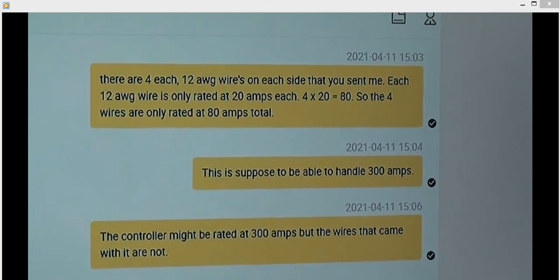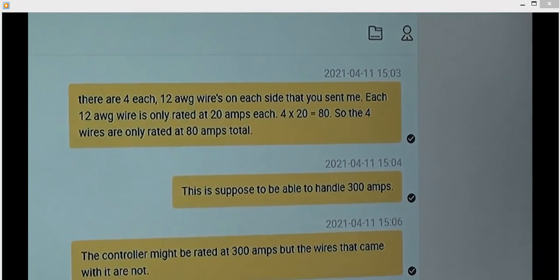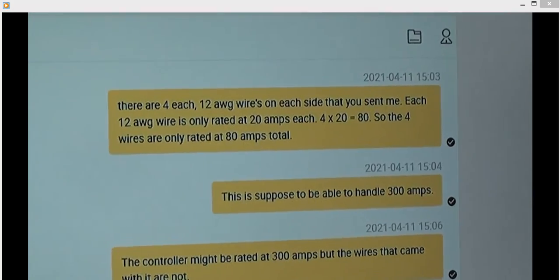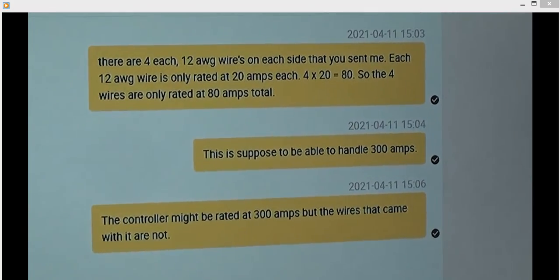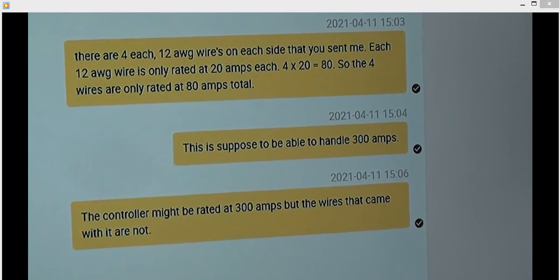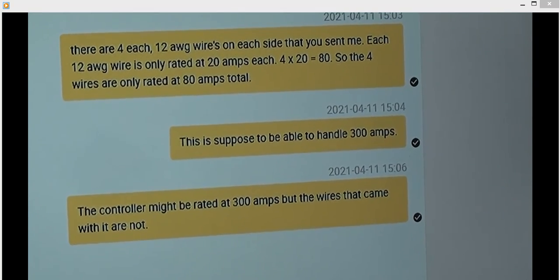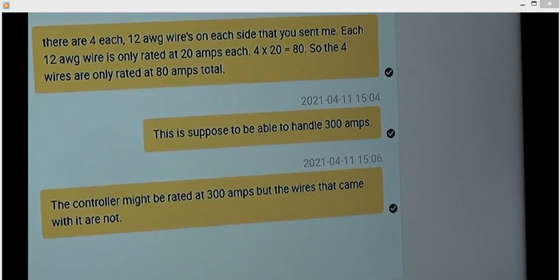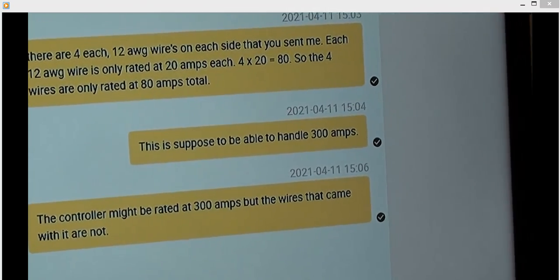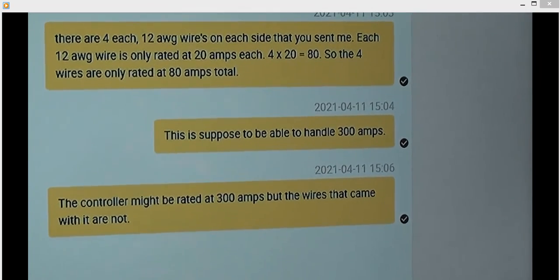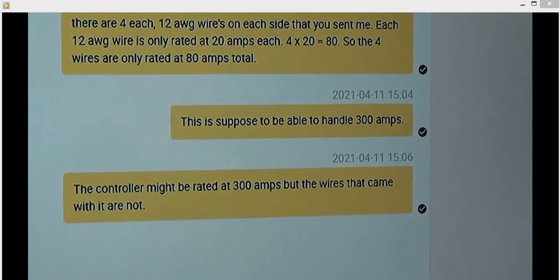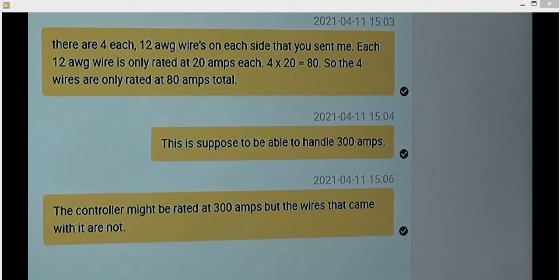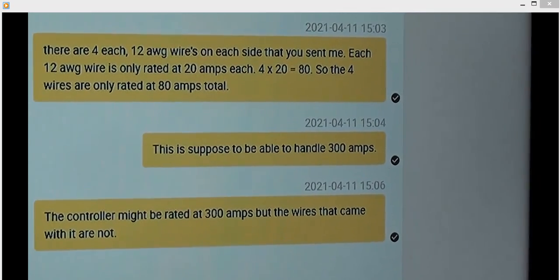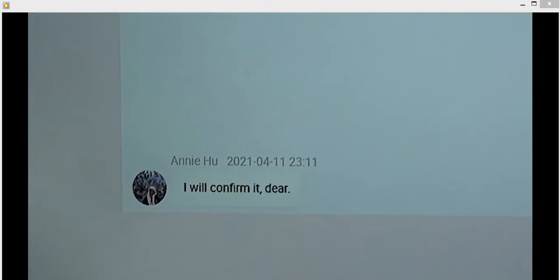There are 4 each 12 AWG wires on each side that you sent me. Each 12 AWG wire is only rated at 20 amps each. 4 times 20 equals 80. So the 4 wires are only rated at 80 amps total. This is supposed to be able to handle 300 amps. The controller might be rated at 300 amps, but the wires that came with it are not. I will confirm it, dear.